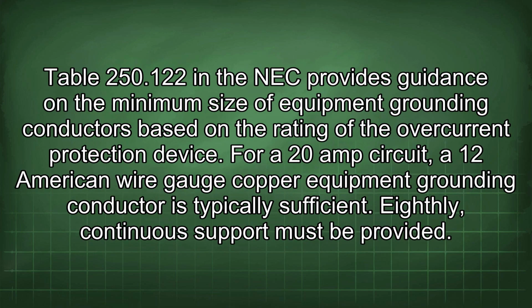Table 250.122 in the NEC provides guidance on the minimum size of equipment grounding conductors based on the rating of the overcurrent protection device. For a 20 amp circuit, a 12 American wire gauge copper equipment grounding conductor is typically sufficient.